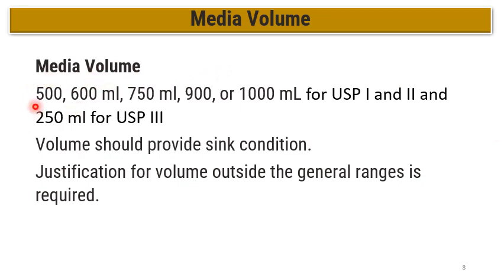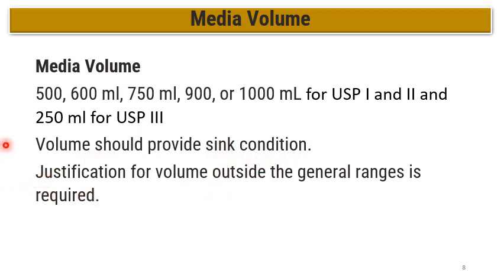Regarding media volume: generally 500, 600, 750, 900, or 1000 mL are used for USP-1 and USP-2, while 250 mL is used for USP-3 apparatus. The volume and pH should be selected such that sink conditions are provided. Generally, sink condition is achieved when three times the strength of the formulation can be dissolved in the media. If media volumes outside the generalized ranges are used, justification is required.